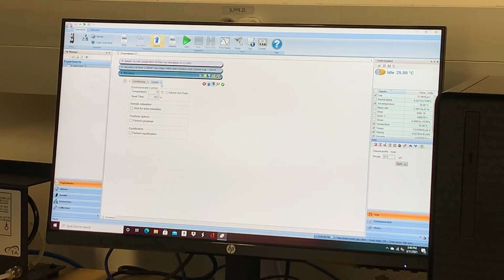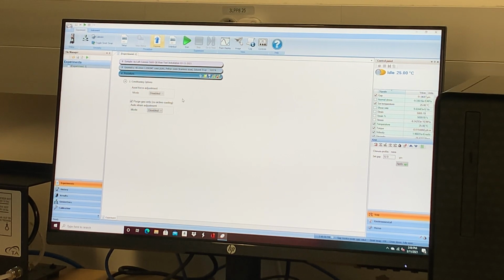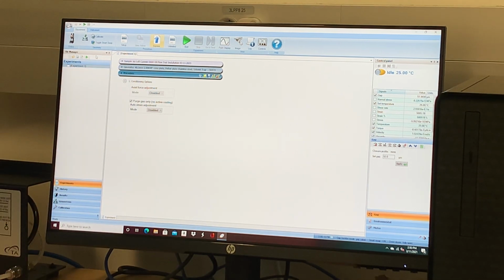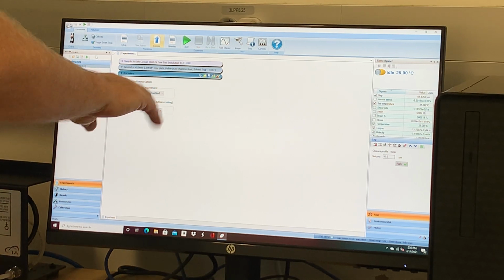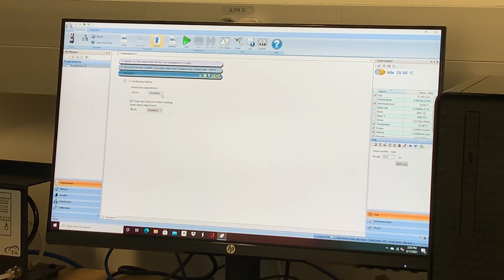You can also, under conditioning, have axial control. So if you had samples that expand or contract, it doesn't sound like you guys will be running stuff like that, but if you did, you can control the axial force of the instrument. A lot of people with carbon fiber composites will use axial control because their samples cure and also contract or expand a lot. Well, we can't do it because it's a cone. You can't run it with a cone, it's got to be a plate.